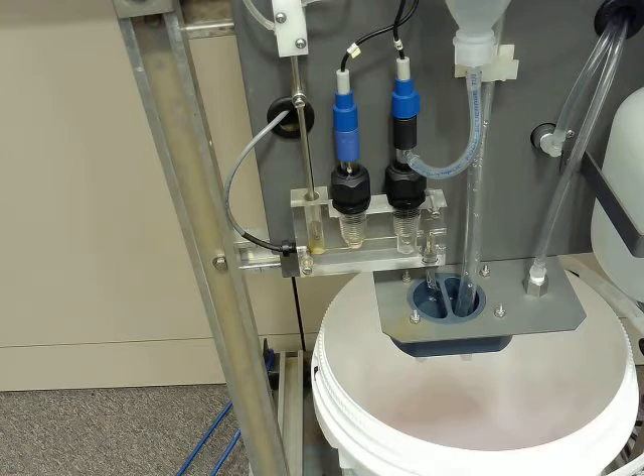It is important to note that even if the tubing to the buffer was just disconnected and open to air, you would also get bubbling, but obviously it wouldn't be appropriate bubbling. But as long as that tube is connected to your vapor, it means you're pulling in your ammonia vapor and buffering your sample. One reason that vapor is important, principle of operation wise: this analyzer acts a lot like a pH analyzer. We've got our 2 electrodes looking for electrical potential in the sample, related to sodium.